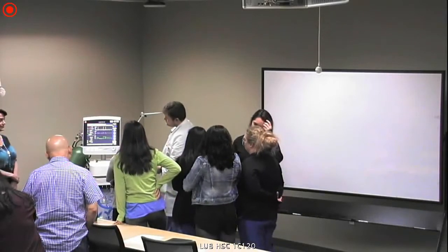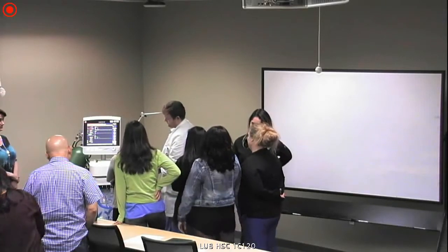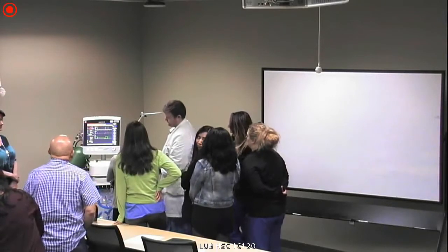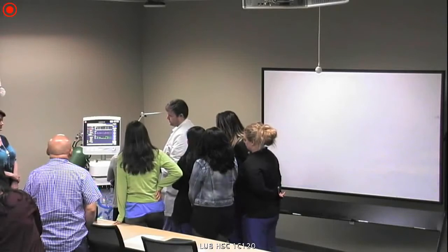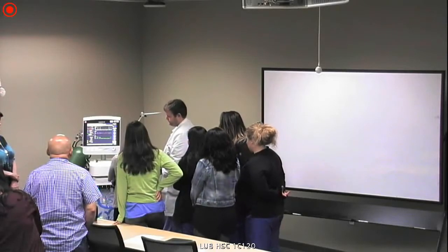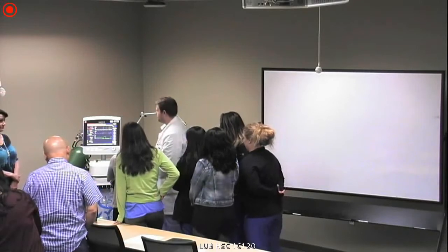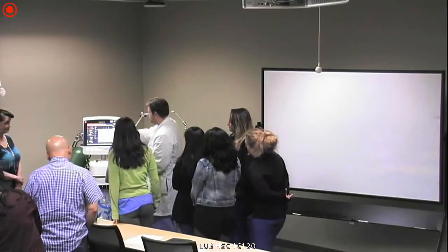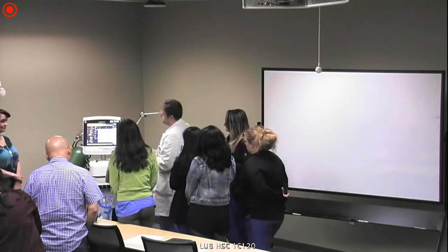So in pressure control, your peak inspiratory pressure you set is going to be your plateau pressure, right? Because you don't have the peak. You're setting a ramp up to a set pressure. You're holding that pressure for the time that you tell it to. So here's your inspiratory time. So you're holding them at a P-high of 35 for 1.3 seconds.